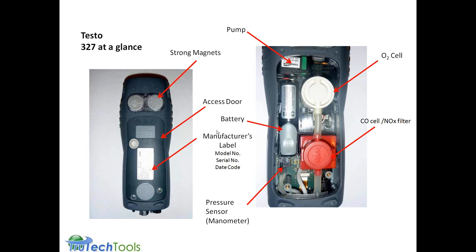And other questions, how long do the sensors last, especially if seldom used? Do the units have something that indicates a need for replacement? Yes, there is a smart process inside the meters, which will tell you when the sensors are approaching the end of the service life. And how long do they last? I would say you can get between 3 and 4 years out of an oxygen sensor, more than 3 years, but into the 4-year, 5-year period. And a CO sensor could last a good 5 to 6 years.